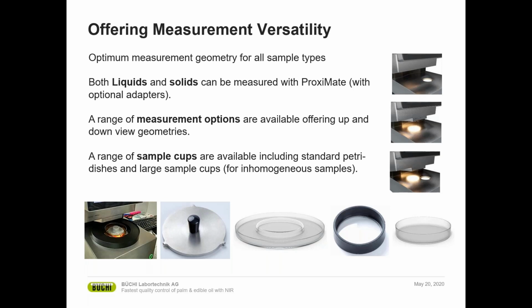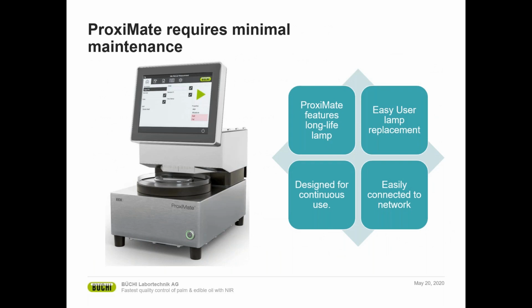In the middle of the slide, at the bottom there, we've got an example of a large sample carrier. A large sample cup, and that can be used with things like fiber measurements, where there might be some inhomogeneous distribution of things like moisture throughout that sample, and that allows larger sample areas to be analyzed by the instrument, providing more accurate results. And that would be used in down view. So you can see we have a wide range of measurement options available for customers working in the palm oil industry. In addition to this, we've designed the instrument to need minimal maintenance.